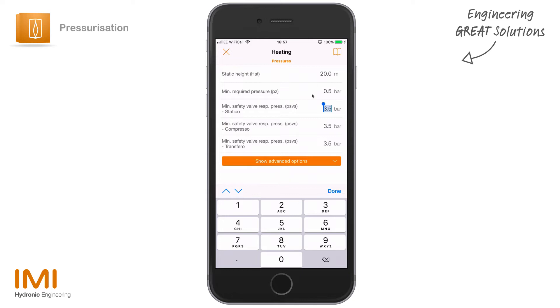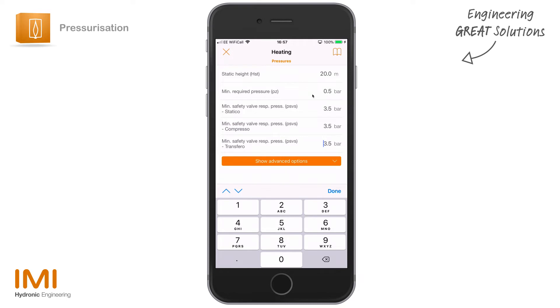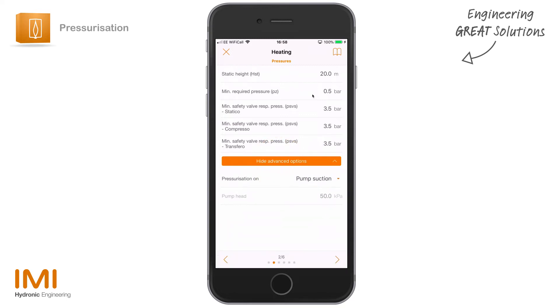We have a safety valve response pressure for a Statico, a Compresso, and a Transfero — those are the three differences you can choose depending on what piece of equipment you think you might select. As we move through the sections you'll be able to choose between these three. If you've got a safety valve response pressure to enter, you can do so — at the moment that's 3.5 bar, which is a relatively standard safety valve pressure. We'll leave it at 3.5 bar.